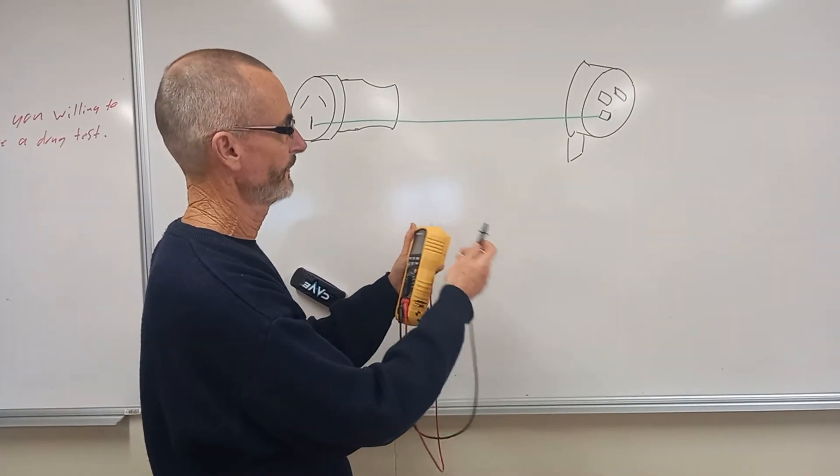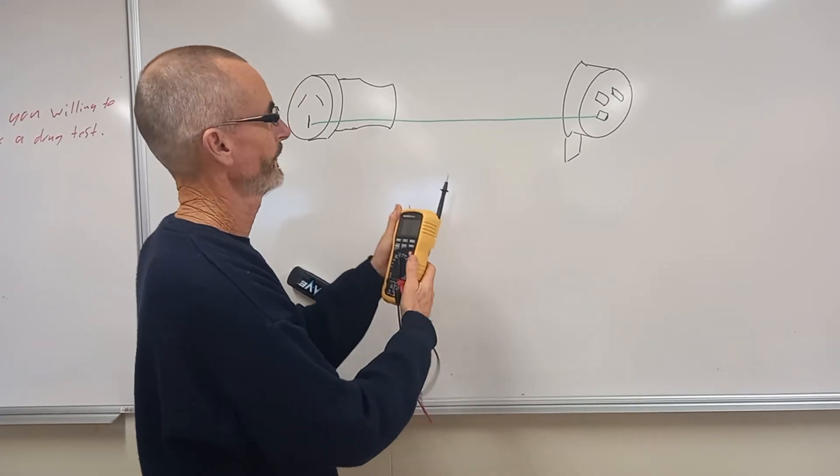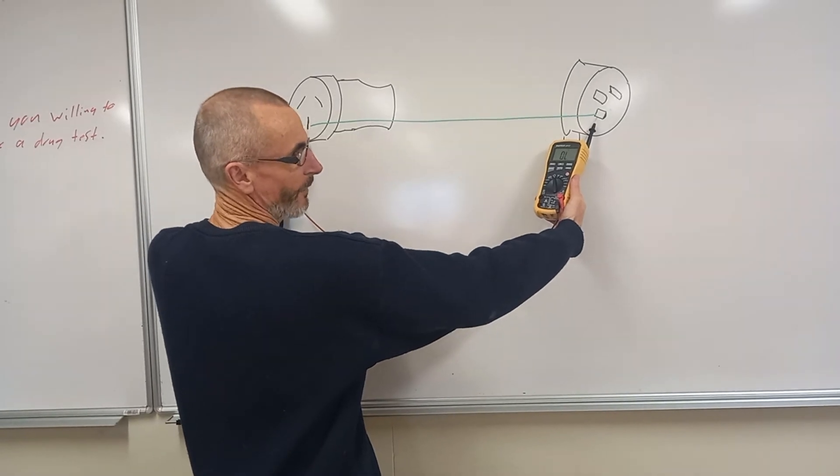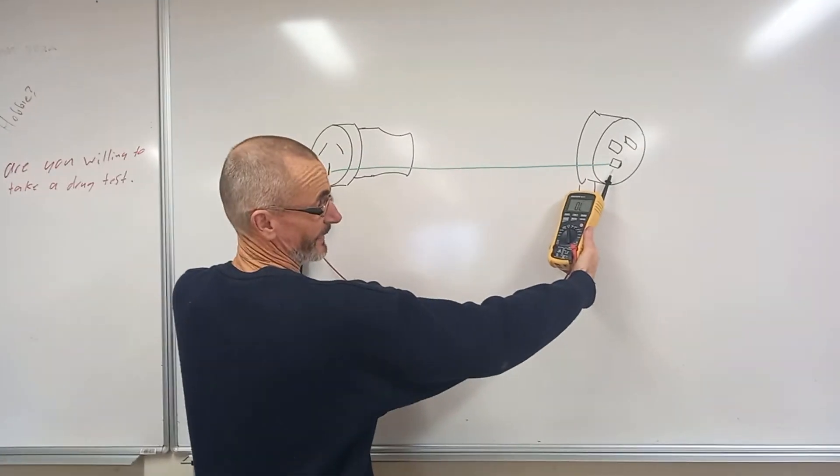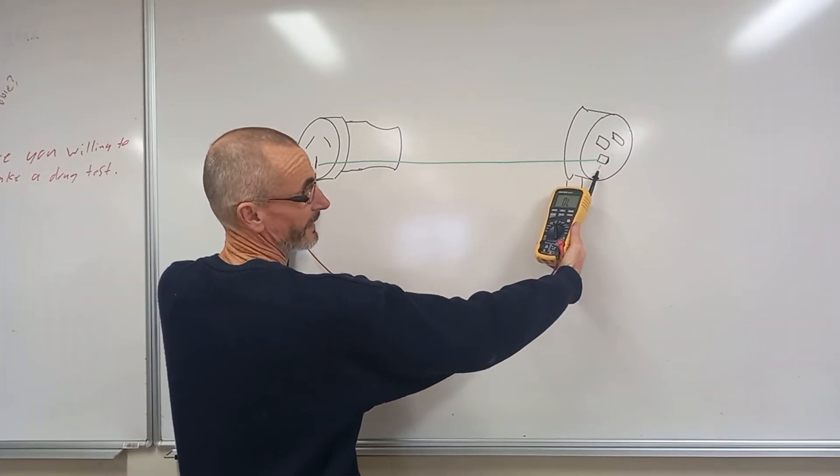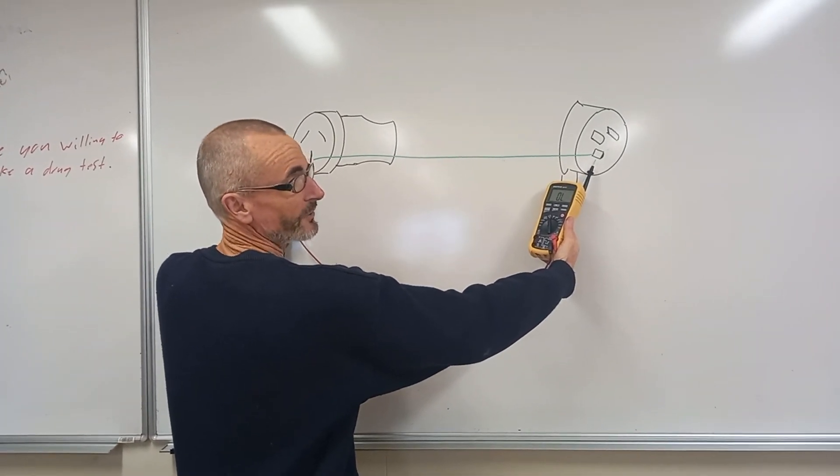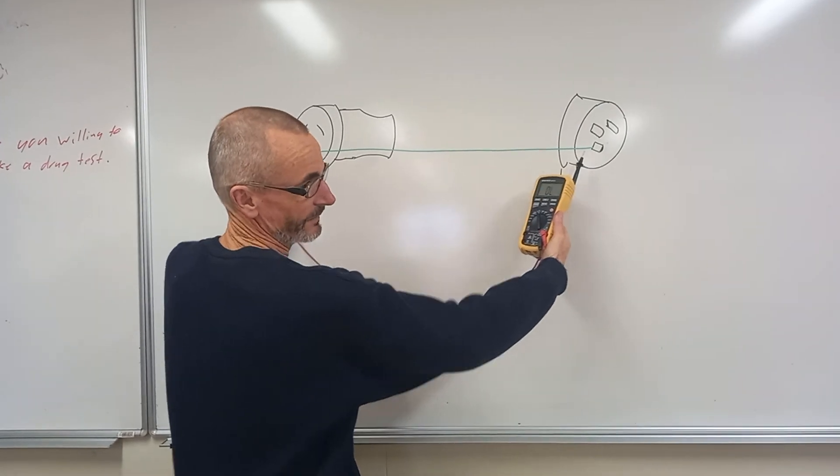So now what I need to do is measure from that point there and that point there. What I expect it will be very low ohms because it's a piece of copper wire. I expect it to be zero or very, very close to it. The highest it's allowed to be is one ohm. Shall not exceed one ohm is the correct expression. That's the test we're going to do now.